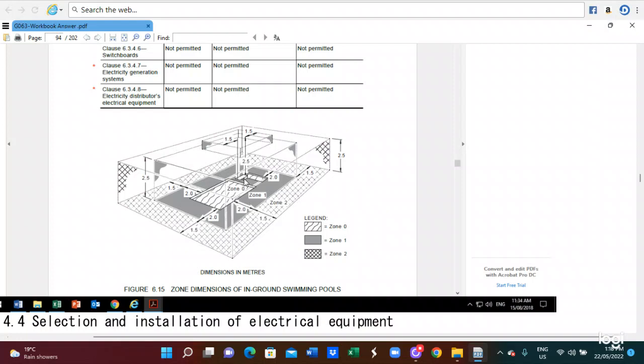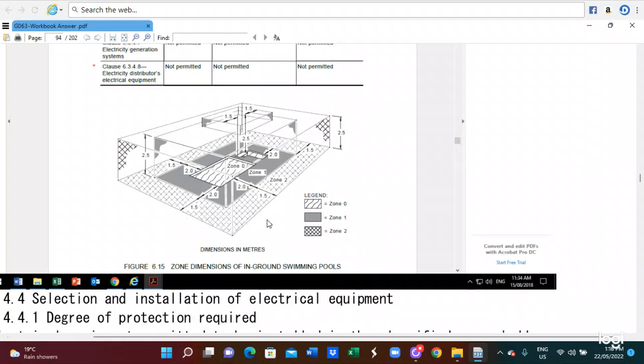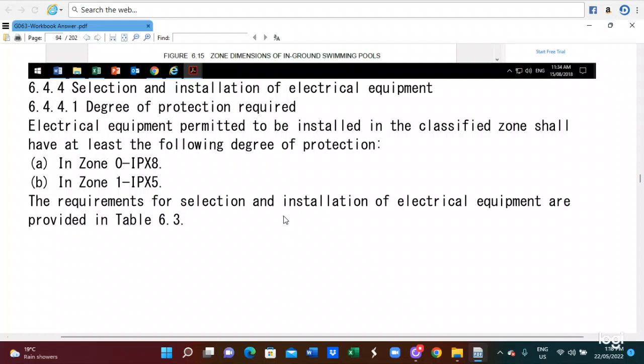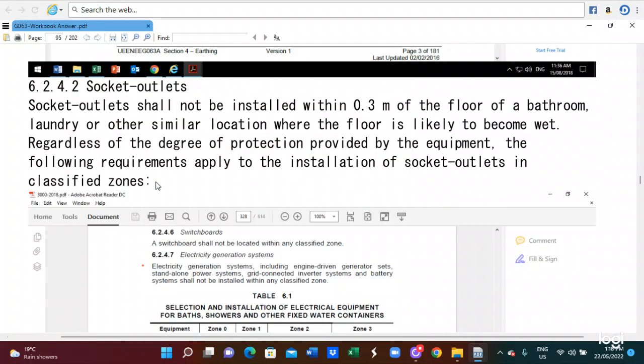So you can see that this is the diagram of the zones. Why is the zone 0? Why is the zone 1, zone 2? You can read in this diagram. Similarly, in the meantime, you also follow clause 6.4.4, selection and installation of the electrical equipment. So clause 6.4.4.1 is the degree of protection required. And also the zone 0 kind of IP protection, zone 1 kind of IP protection, under 6.3. 6.2.4.2 is the socket outlet connection.